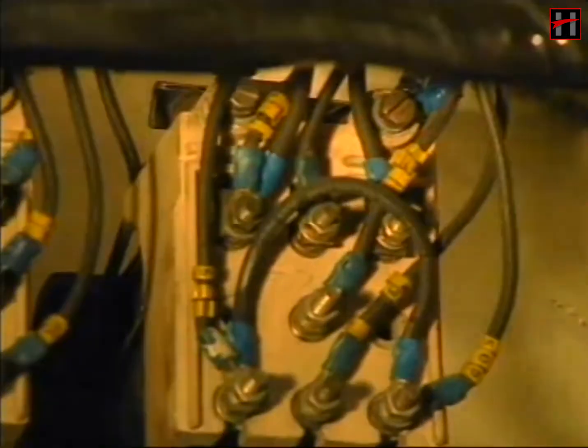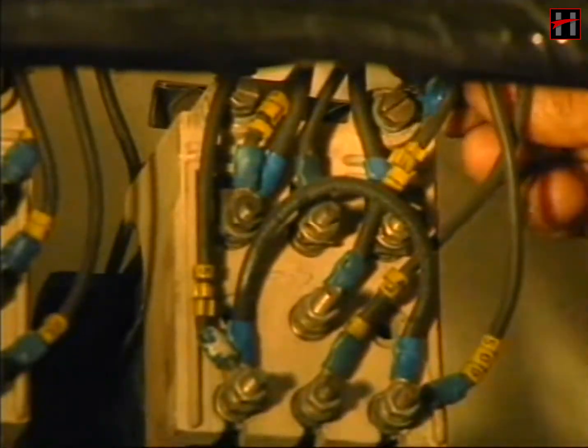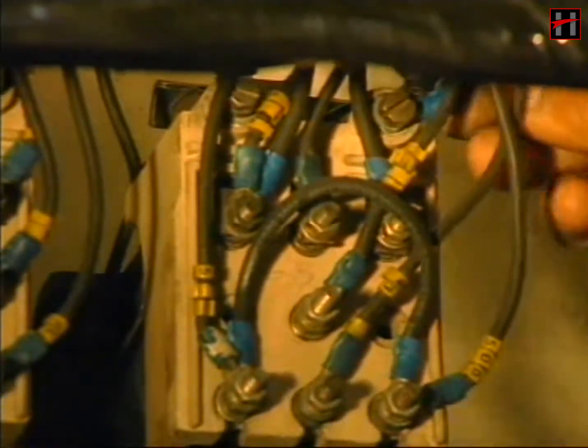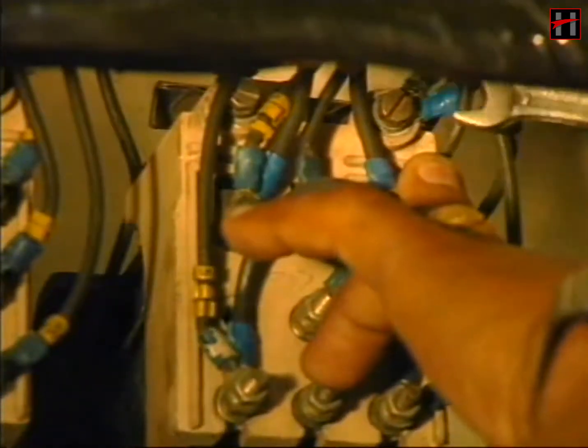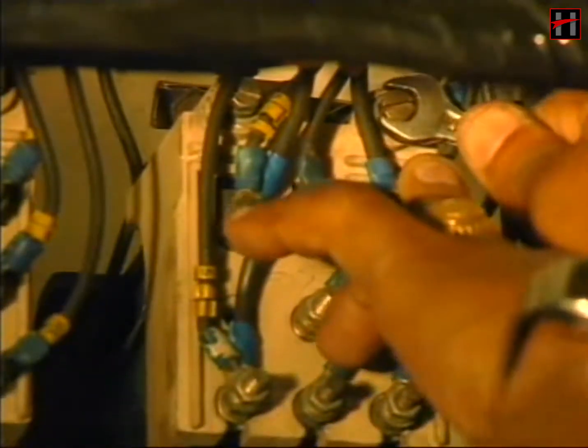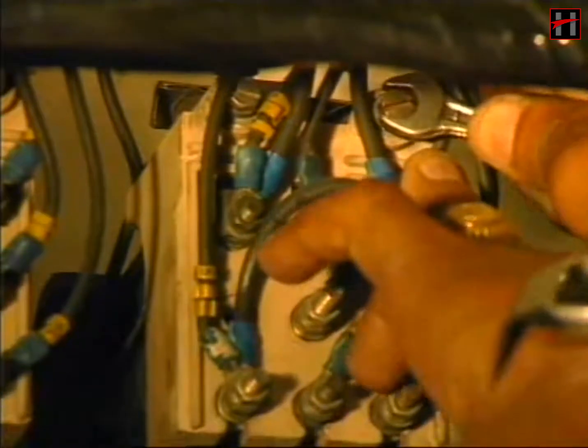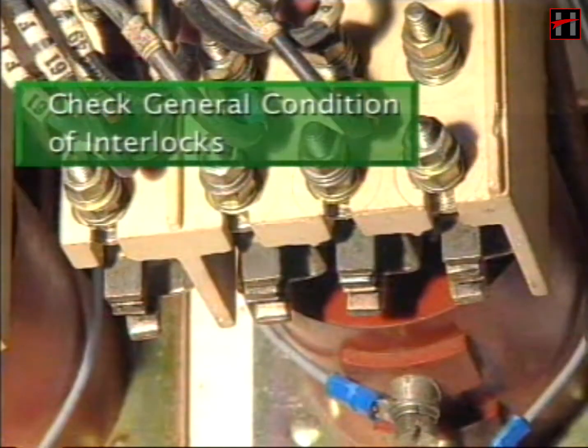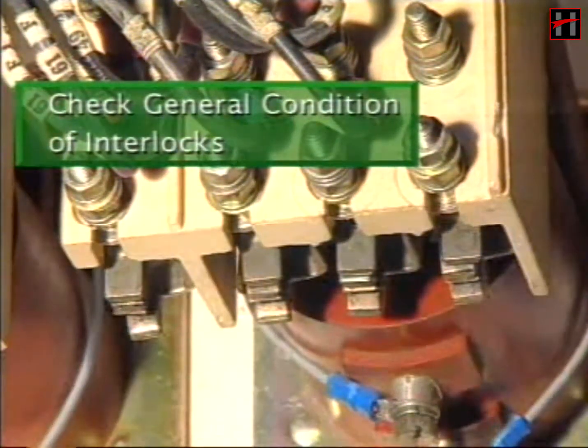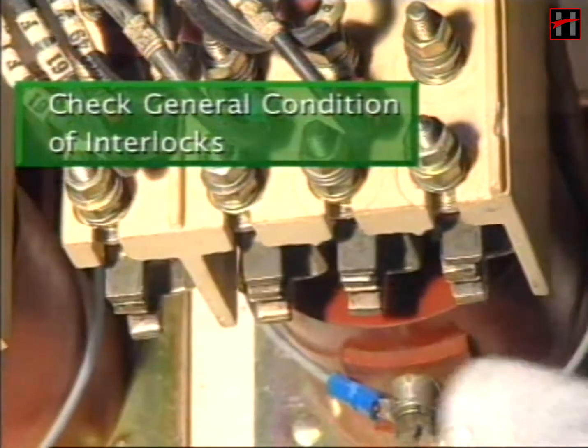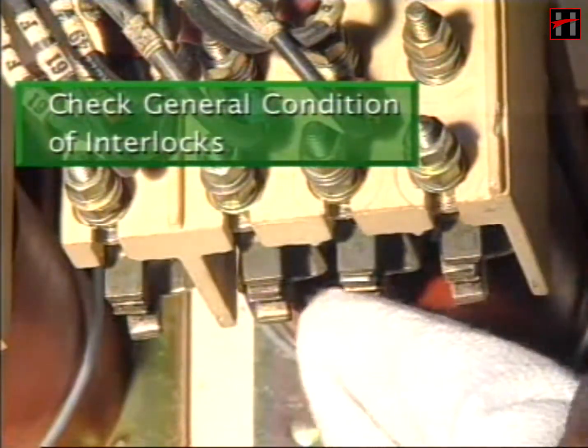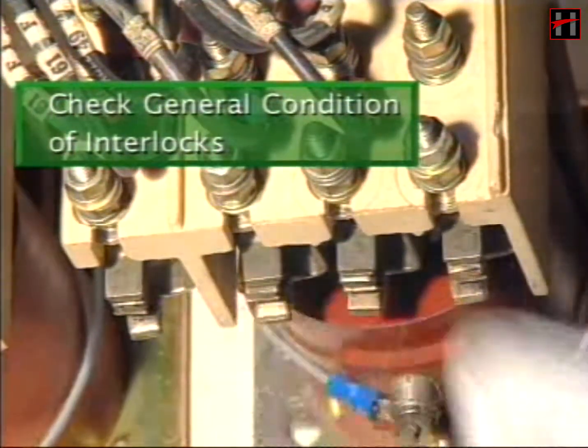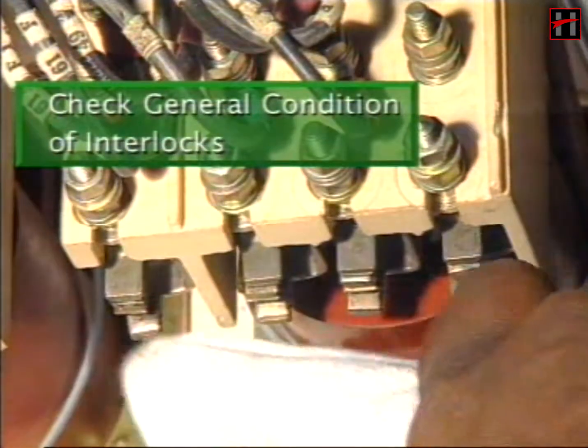Check the terminal connections of all the relays. If any terminal connection is loose or broken, tighten or rejoin connections as required. Check the general condition of the interlocks. If there are flash marks, wear and tear on the fingertips of any interlock, clean the interlock with lintless cloth or emery paper. If required, change the relay.